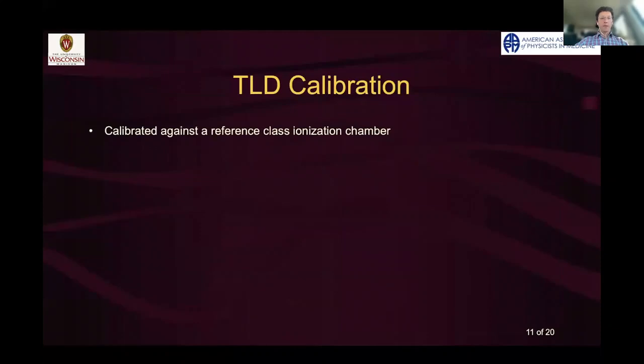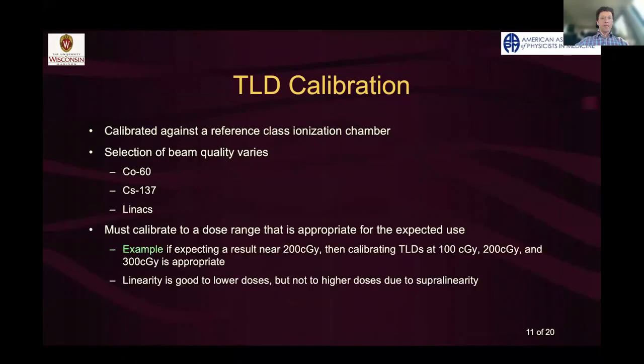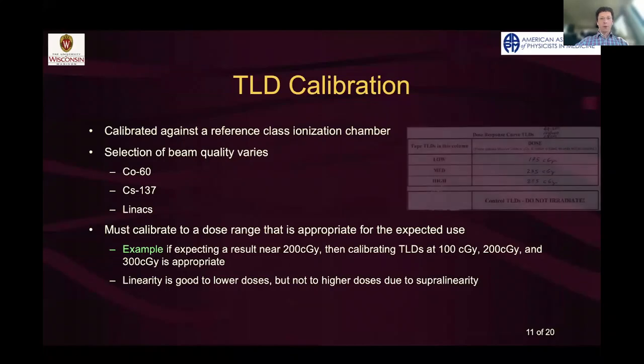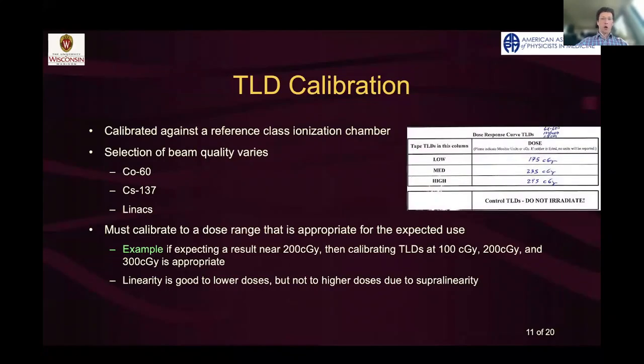The calibration of a TLD is typically done against a reference class ion chamber. You could use a variety of beam qualities. You need to calibrate within a dose range that's appropriate for your expected use. So in the linear range, for example, if you are expecting a result around 2 gray for a typical fractionated treatment, then you'd want to calibrate at 100 centigray, 200 centigray, and 300 centigray, and create a response curve. You can actually extrapolate down to lower doses pretty easily. We do that with our services, if they get a really low dose, but not really to higher doses very easily because of the superlinearity.